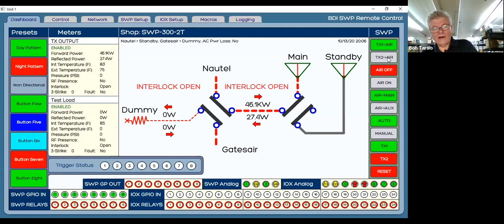Of course, that would be integrated into the transmitter. When I call to move the switch, it would open the interlocks to both transmitters and do a TX off, and then it would move. Then it would look at the power meter, make sure the power's not there, and then allow the switch to move. That's what we call the smart switch technology we've always had in our power meters and motorized switch controller product for years. We integrated that into the new product as well.